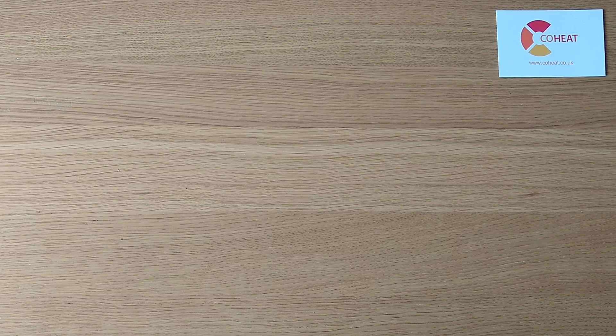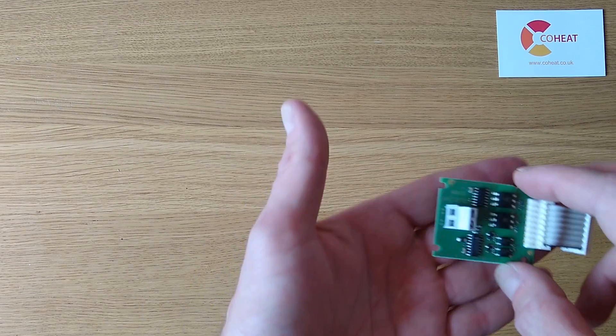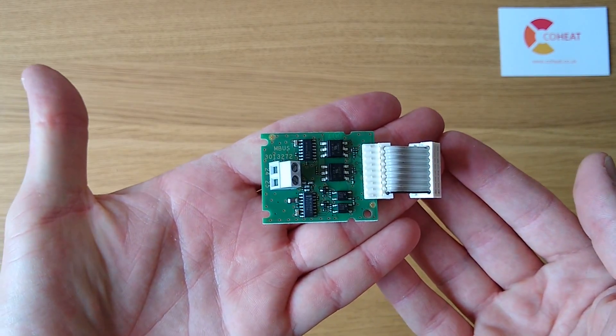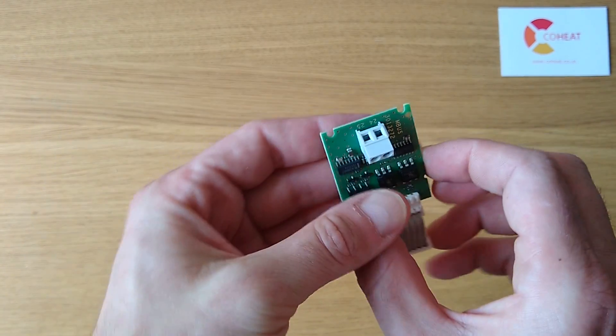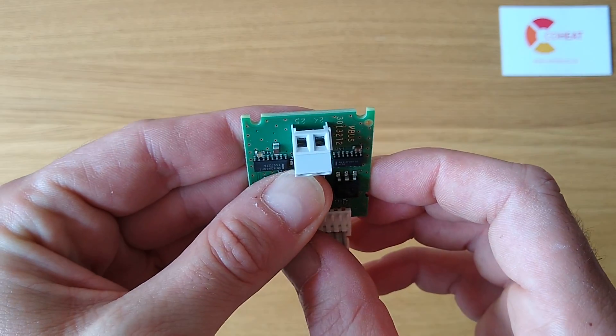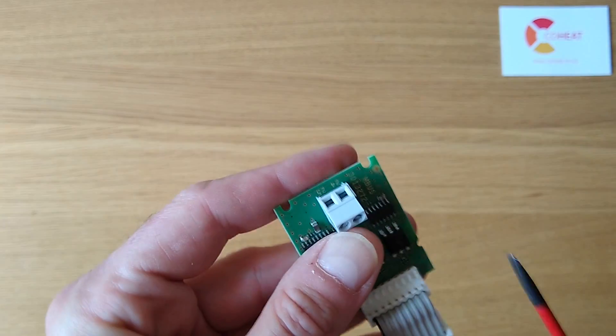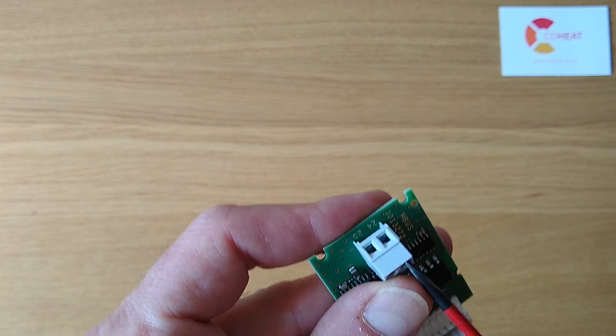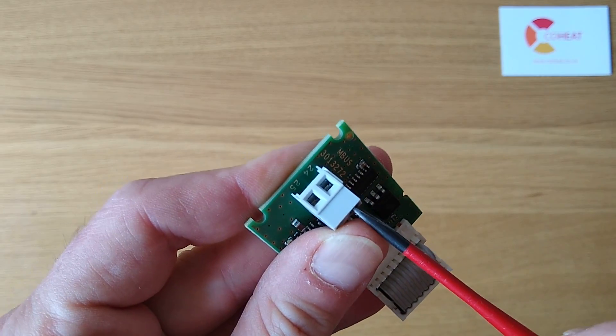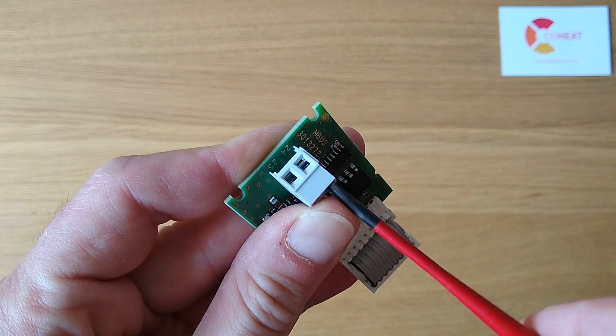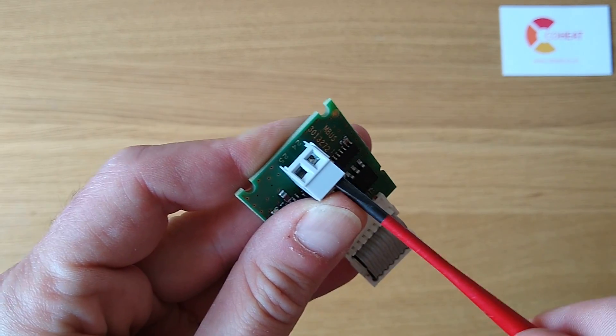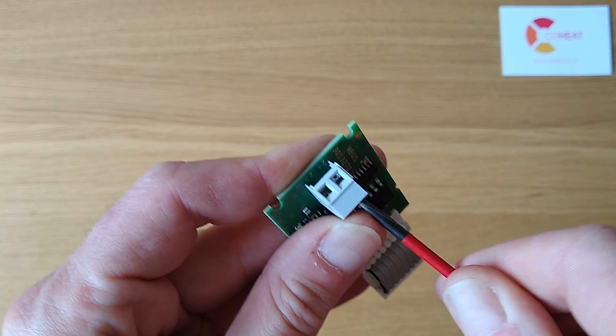Now I'll show you some of the connector types that can be used. Some of the most common MBUS data cards have terminal blocks on them. These terminal blocks have a cage, where as the screw moves, the entire cage moves. This makes them good at trapping all of a cable.